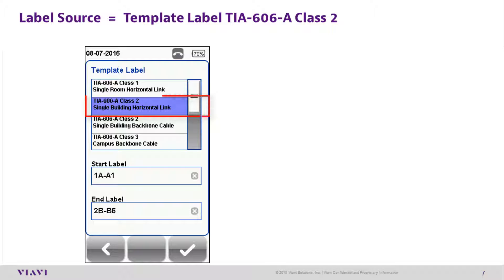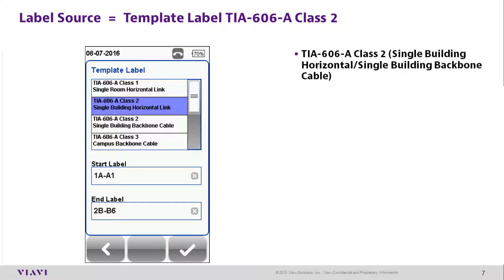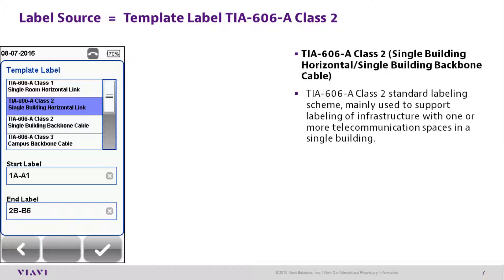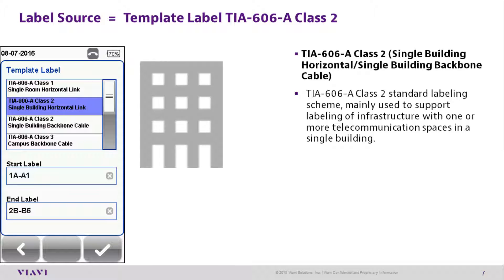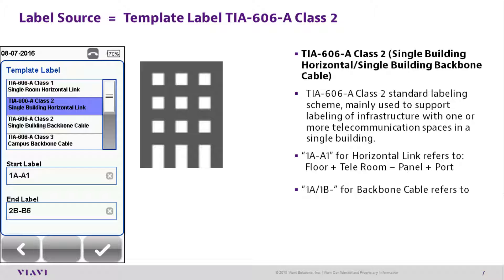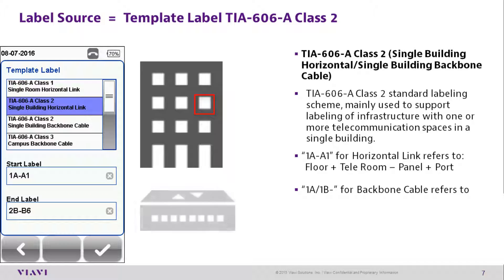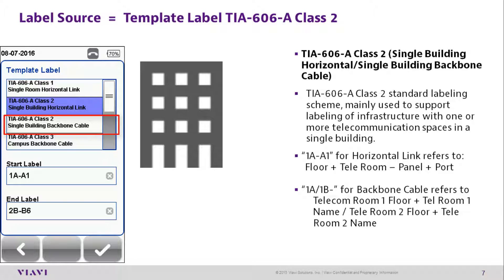Template Label TIA606 Alpha Class 2 covers Single Building Horizontal and Single Building Backbone Cable. This standard labeling scheme is mainly used to support labeling of infrastructure with one or more telecommunication spaces in a single building. 1-Alpha-dash-Alpha-1 for horizontal links refers to the floor, the name of the first telecommunications room, the panel, and the port.